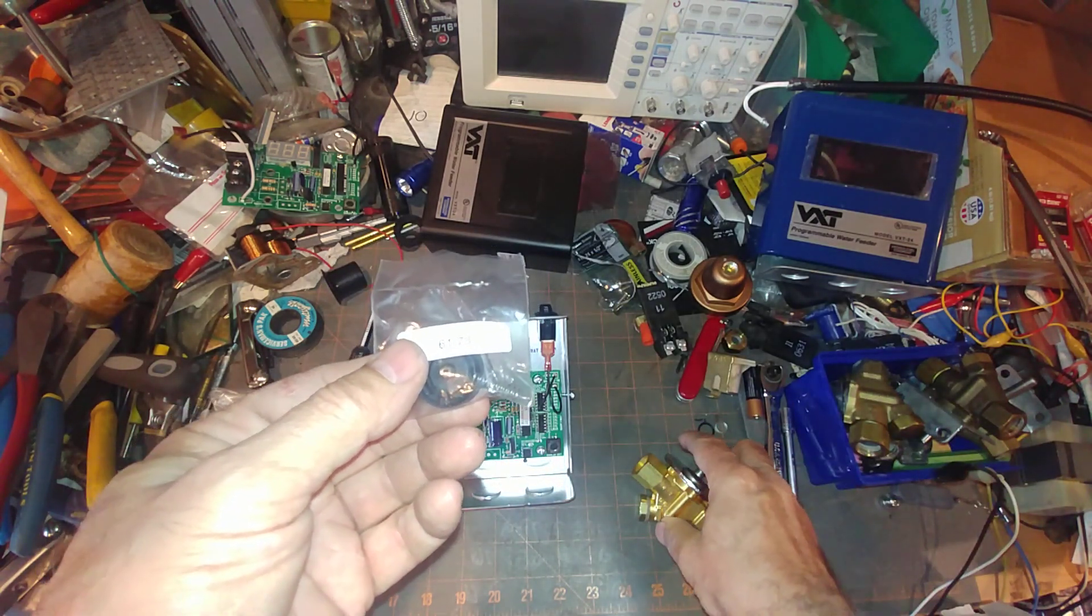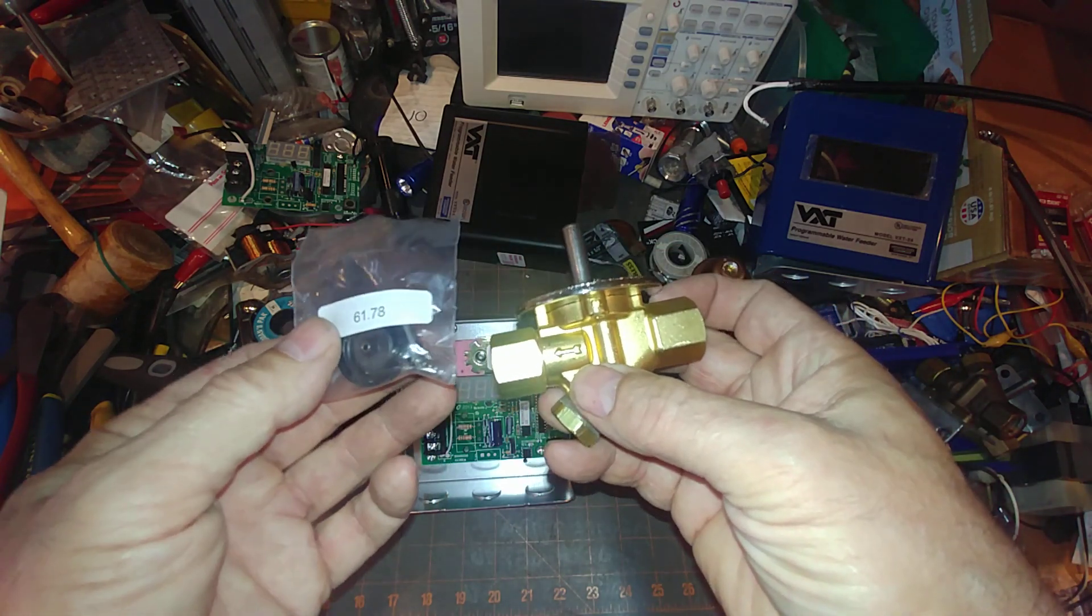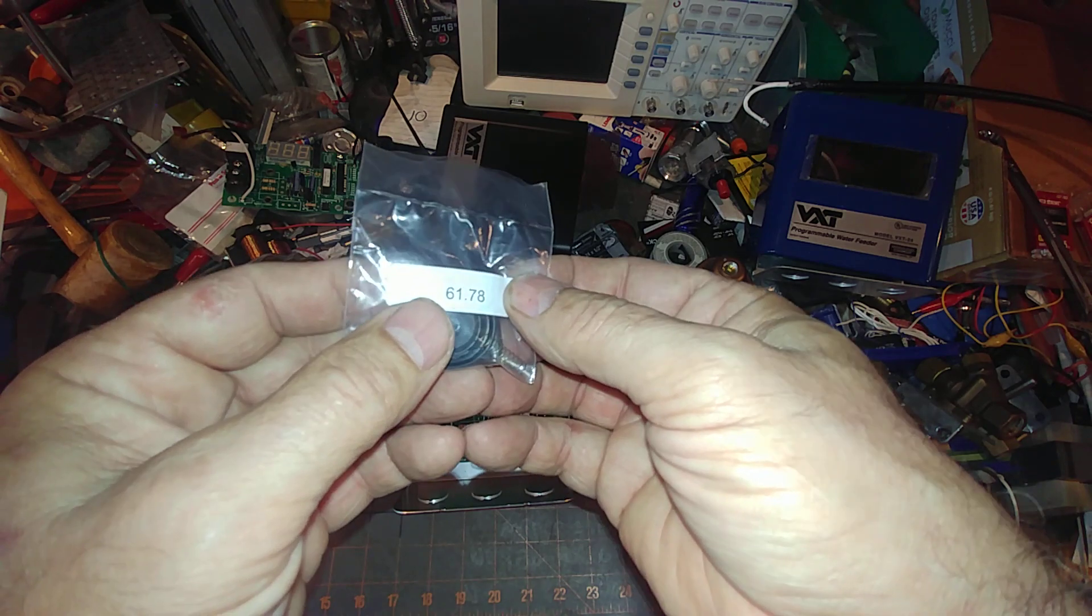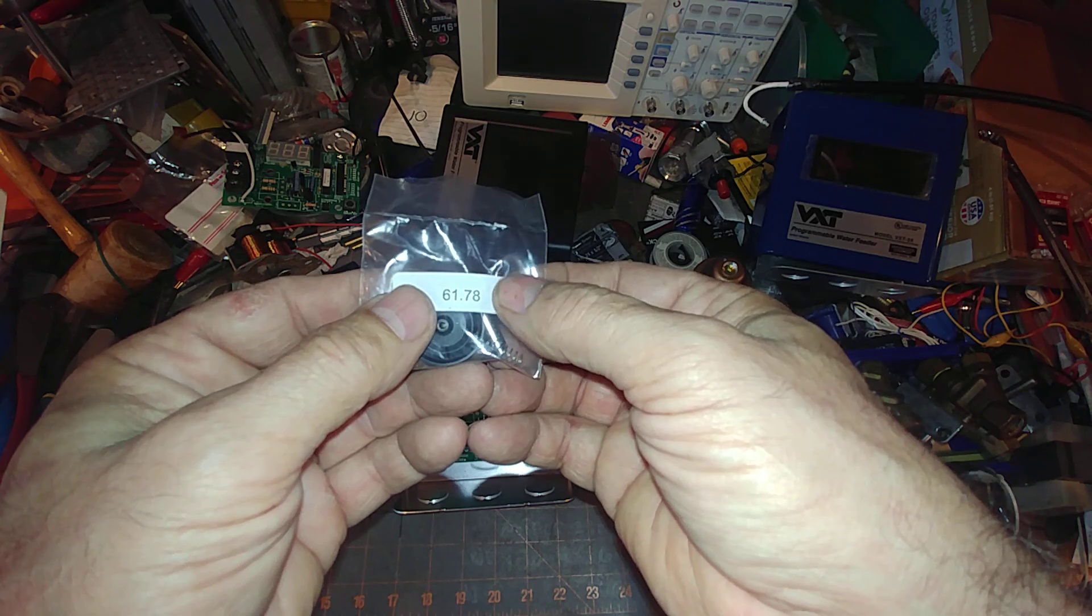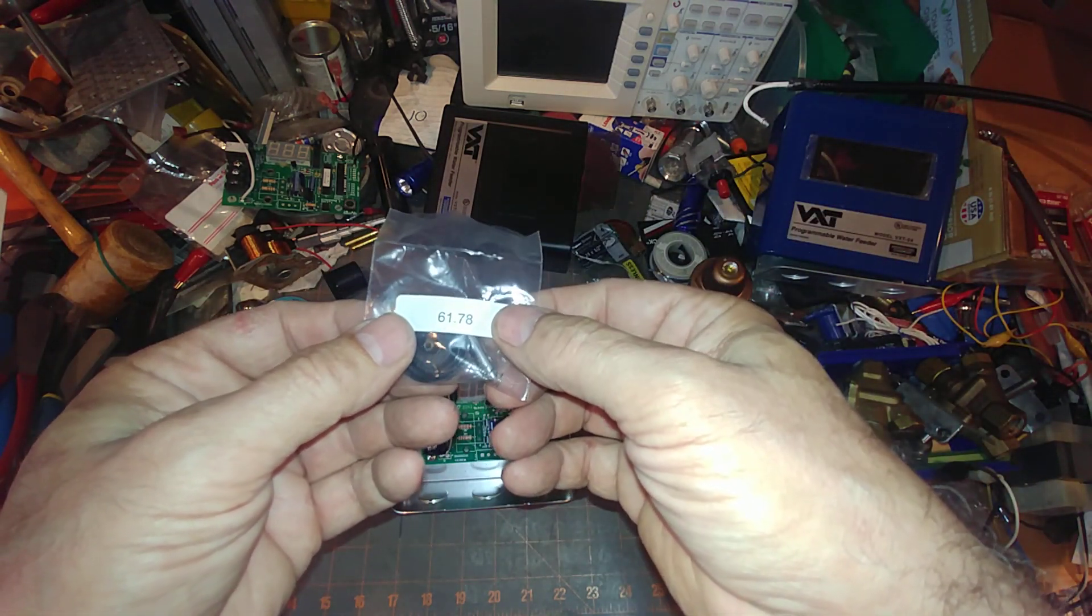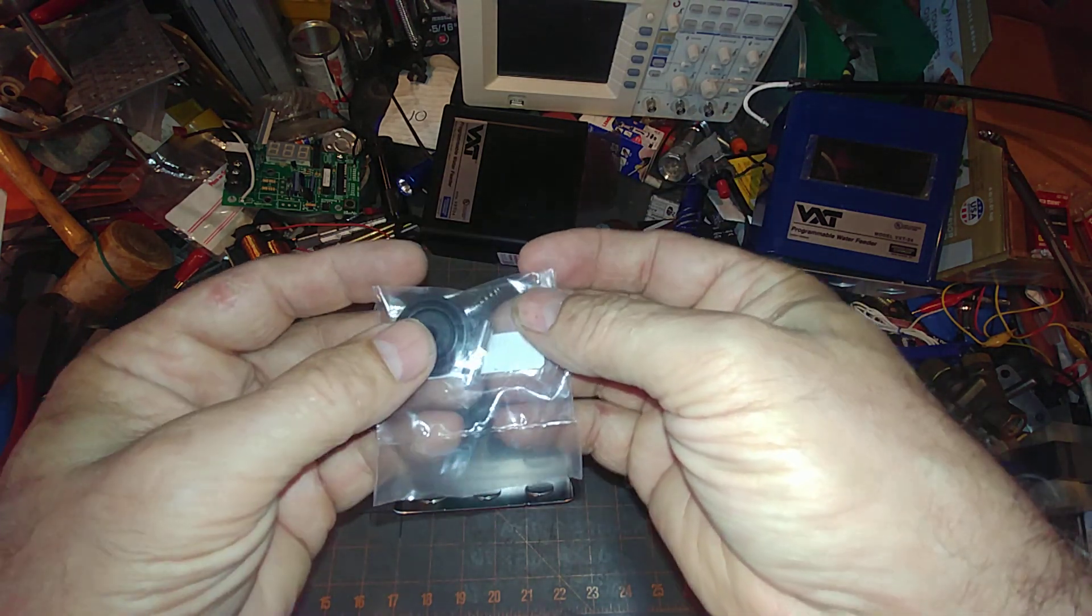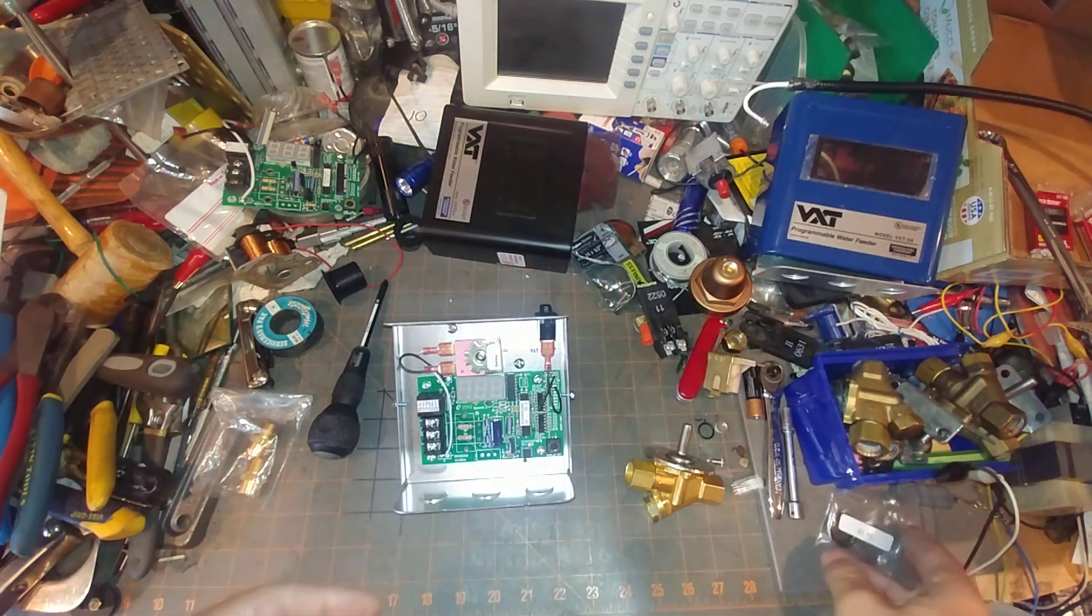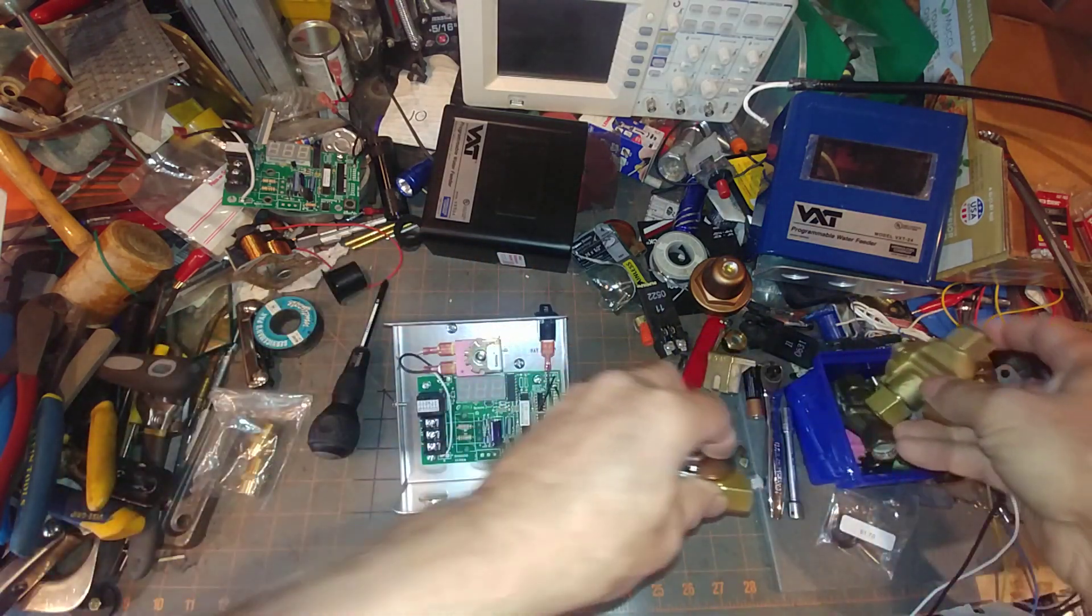This kit here is for the old DEMA 443 valve, but I have done experiments out in the field, and it's a direct clone. This is much more readily available. I think you can get it through CleanRite, which is an automobile washing service supply company. They're fairly inexpensive. I don't know about the spring and the plunger, but I do know the gasket works in both of these valves.